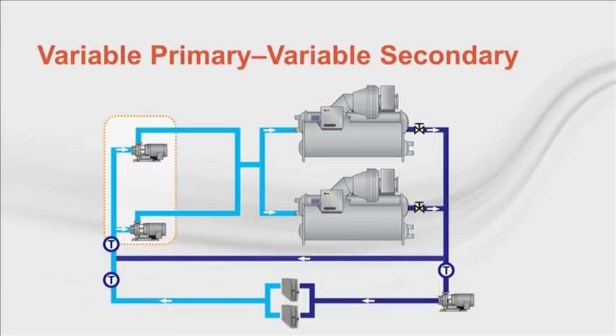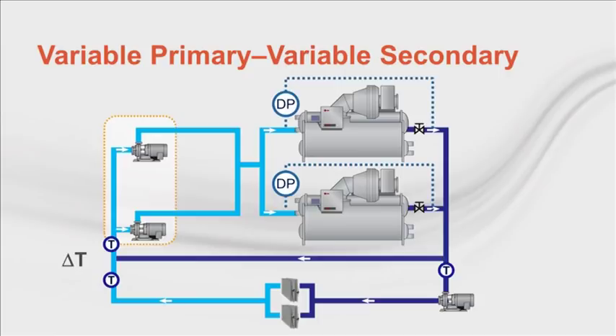Next, install temperature sensors in the return line from the system and to the chiller. Decoupled systems may have these already. Control the pump's VFDs so that the return temperature to the chillers is a degree or two lower than from the system. This ensures a little excess flow in the bypass line all the time, and more importantly, that the system chilled water set point is always maintained. Finally, install flow sensing devices such as DP sensors at each chiller to ensure minimum flow rate. If the temperature control of the pump VSD results in flow approaching the chiller's minimum, this sensor will speed up the drives on the pumps.